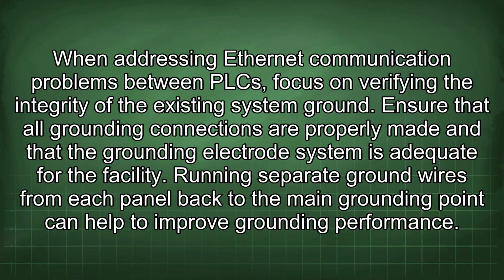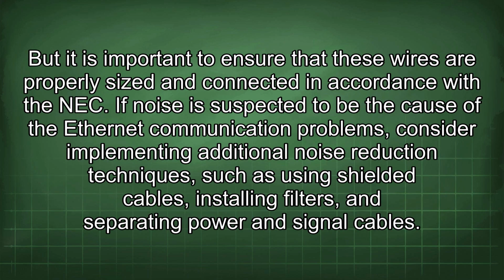When addressing Ethernet communication problems between PLCs, focus on verifying the integrity of the existing system ground. Ensure that all grounding connections are properly made and that the grounding electrode system is adequate for the facility. Running separate ground wires from each panel back to the main grounding point can help to improve grounding performance, but it is important to ensure that these wires are properly sized and connected in accordance with the NEC.